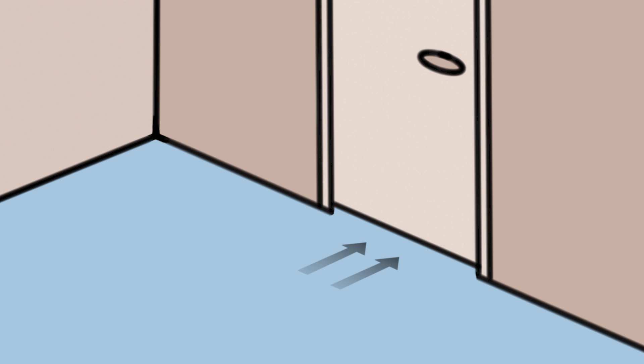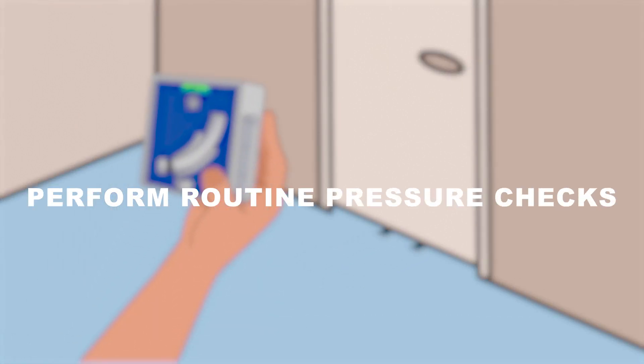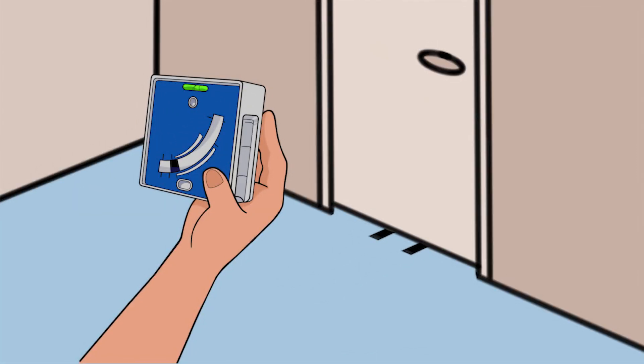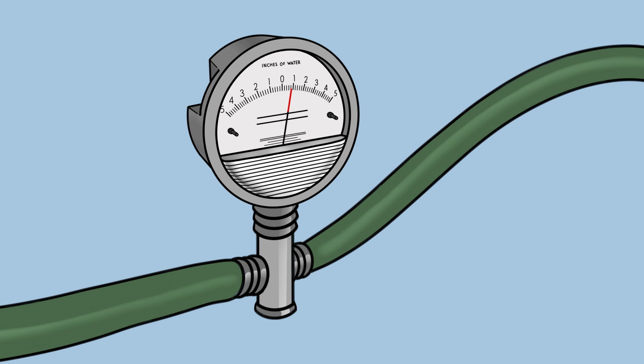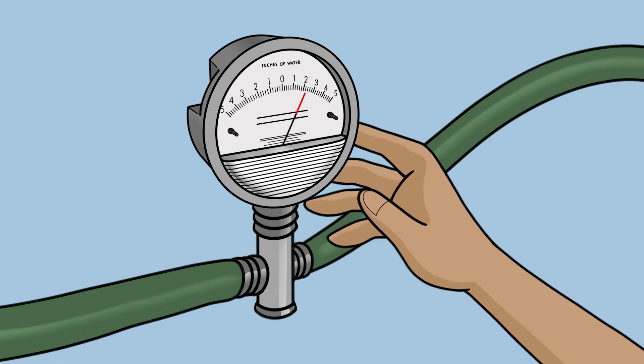It is also very important for the facility's operations team to perform routine pressure checks according to the facility's policy. Additionally, planned preventive maintenance on the HVAC system is important to ensure the room remains negative. Since HVAC systems designed for AII rooms serve high-risk areas, it is also a best practice to perform an annual test and balance, or TAB, on the system and calibrate any diaphragm-based pressure sensors to ensure that the room is truly performing as intended.